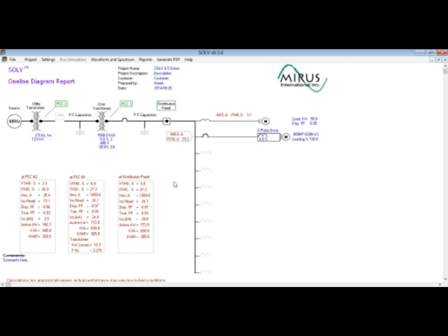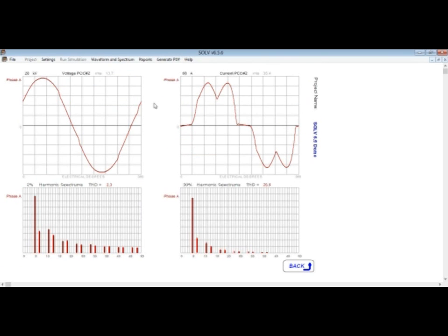You can see current distortion at the VFD load branch is above 29%, and the voltage distortion at the user transformer is 6.8%. But the true power of SOLV is in the extensive information available for analysis after this calculation. So let's begin with waveform and spectrum graphs. So when you click on the top menu for waveform and spectrum and select PCC number 2, we can see waveforms and spectrums window open.